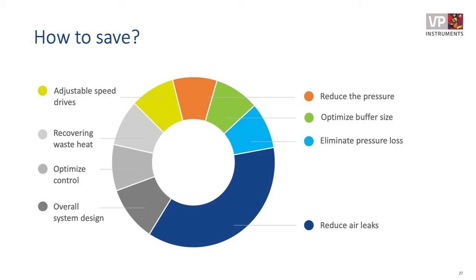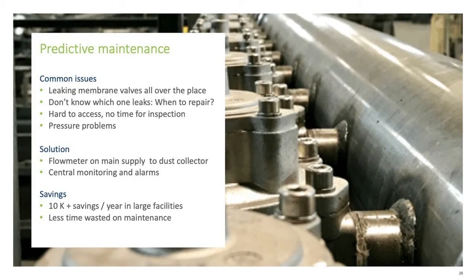But now let's go to the first example case, which is predictive maintenance on dust collectors. Dust collectors are used in many industrial sites, basically to collect dust from processes. In those dust collectors, there are filters which are typically cleaned out with a shock of compressed air, a sort of shock wave. These dust collectors have very common issues, like the membrane valves they use to create those pulses of compressed air. They tend to leak over time. There is a rubber seal inside, which eventually will start to crack. But in a lot of cases, you don't know which one leaks when, and when to repair it. So often this is neglected for too long.